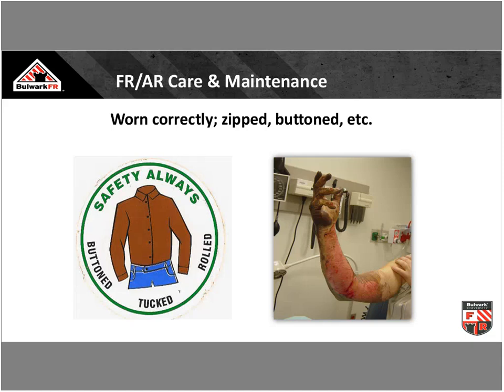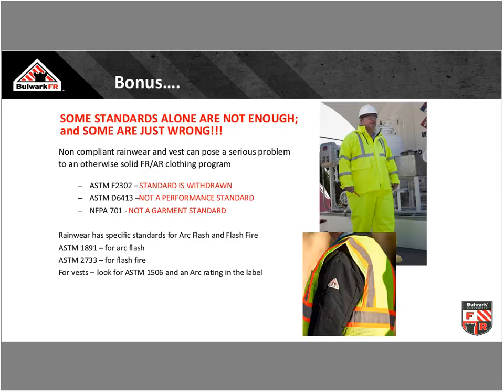The picture on the right, unfortunately, that was a verification error. Failure to verify the absence of voltage. We went in and turned off the piece of equipment, came back, rolled up the sleeves of our perfectly good arc-rated shirt, because you can see where it was rolled up to and where it performed. We took off our rubbers and leathers, and we proceeded to do what we thought was de-energized work. As you can see, it was not. This little safety tag here goes on all the hard hats of a number of utilities that I've visited, and it simply says buttoned, tucked, and rolled to remind the guys how to properly implement their PPE on a day-to-day basis. Just a real quick bonus, and we're getting right up here on Q&A time.